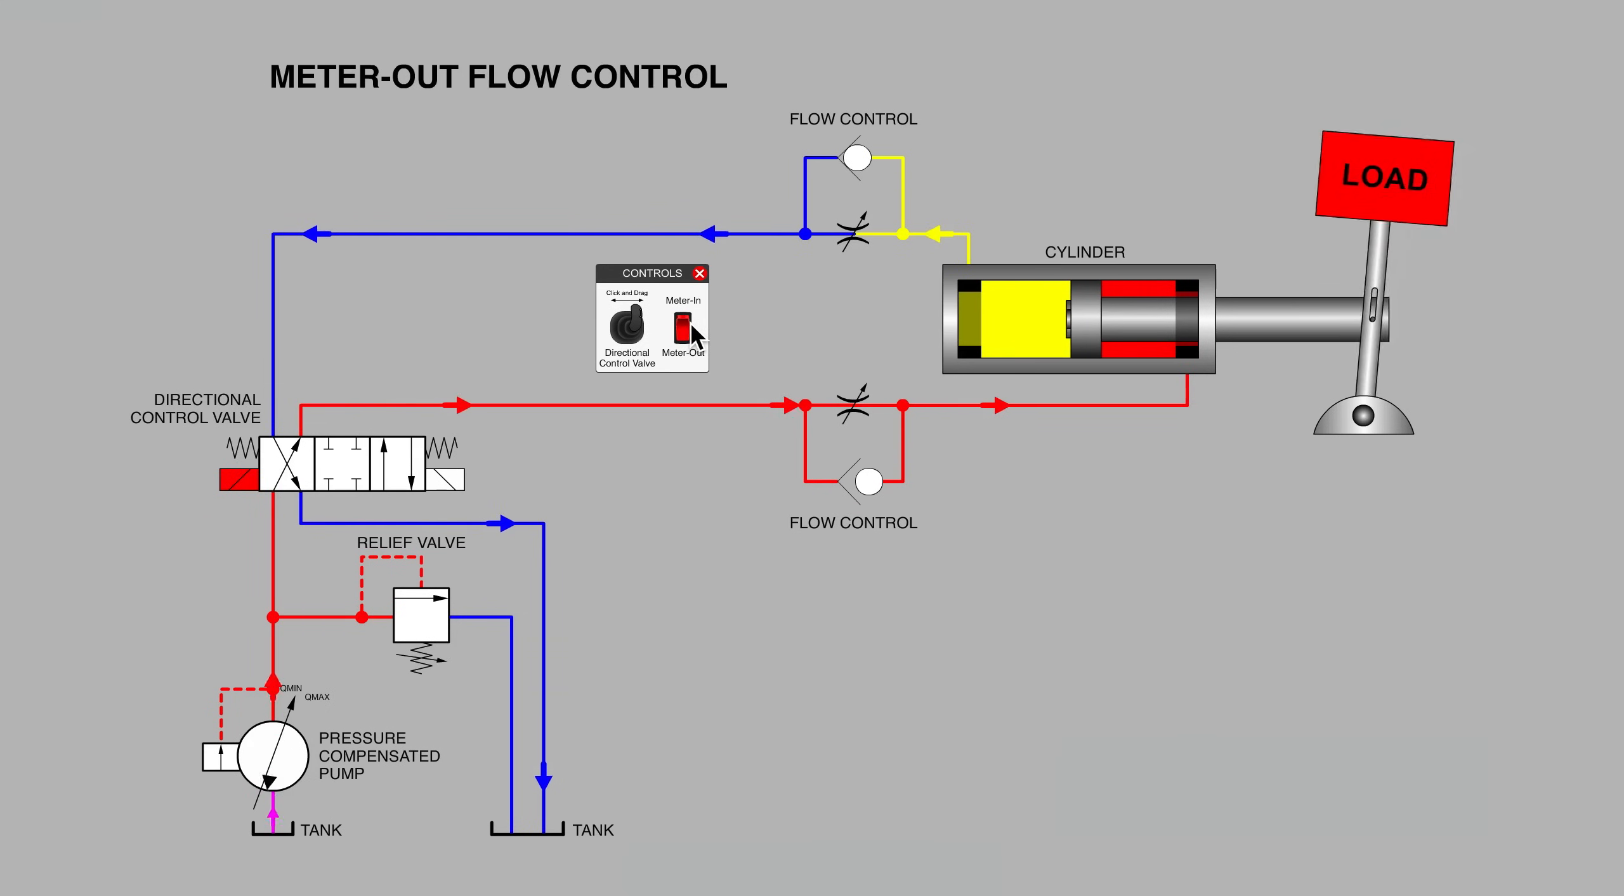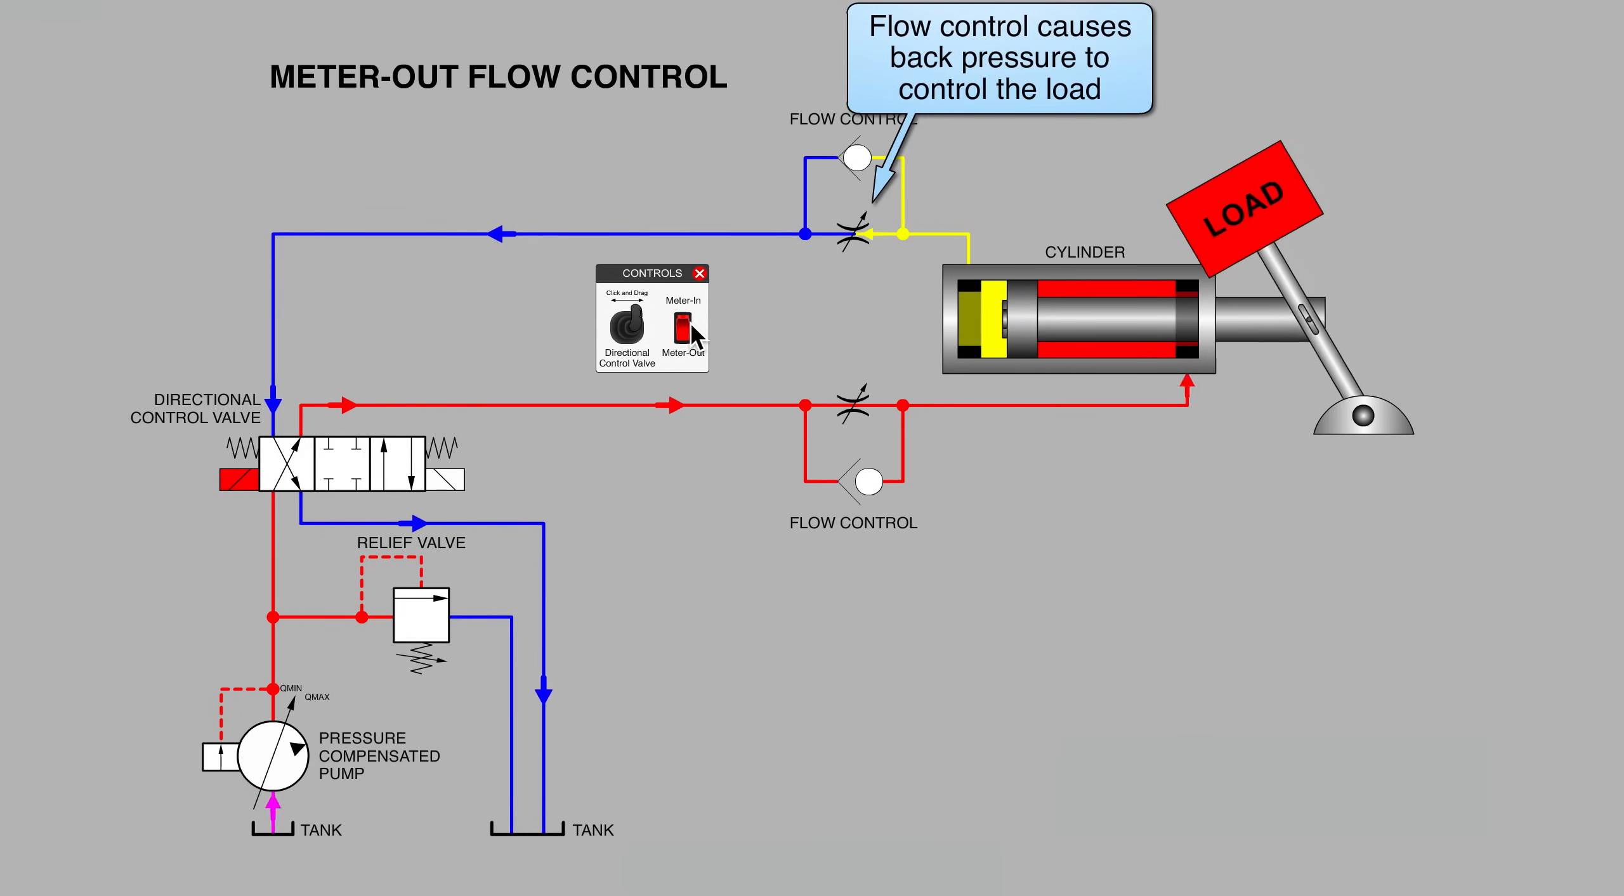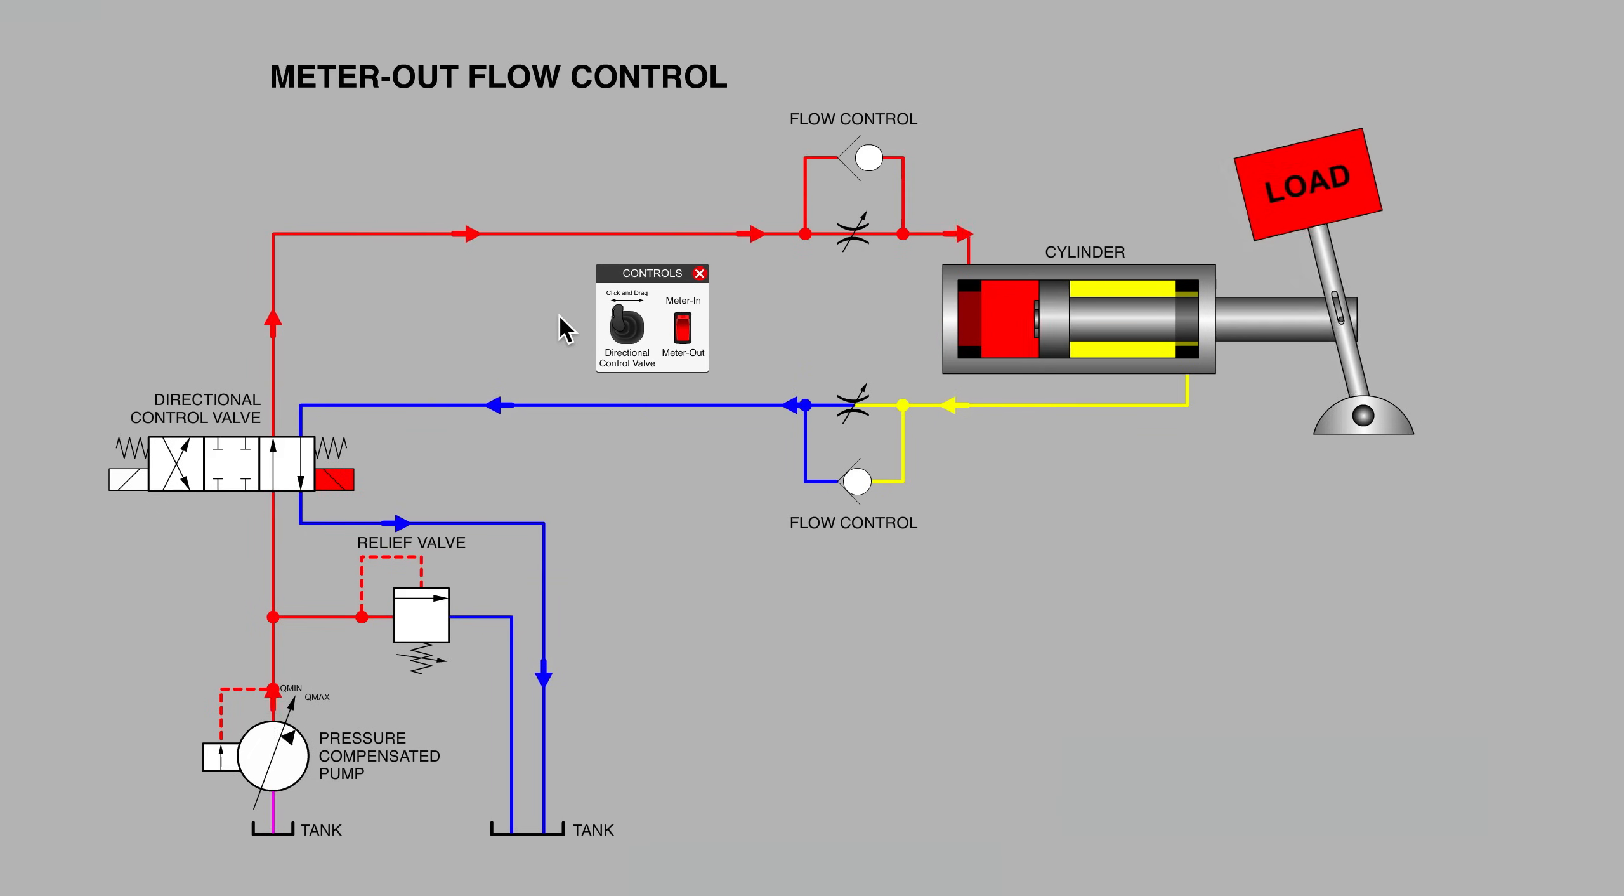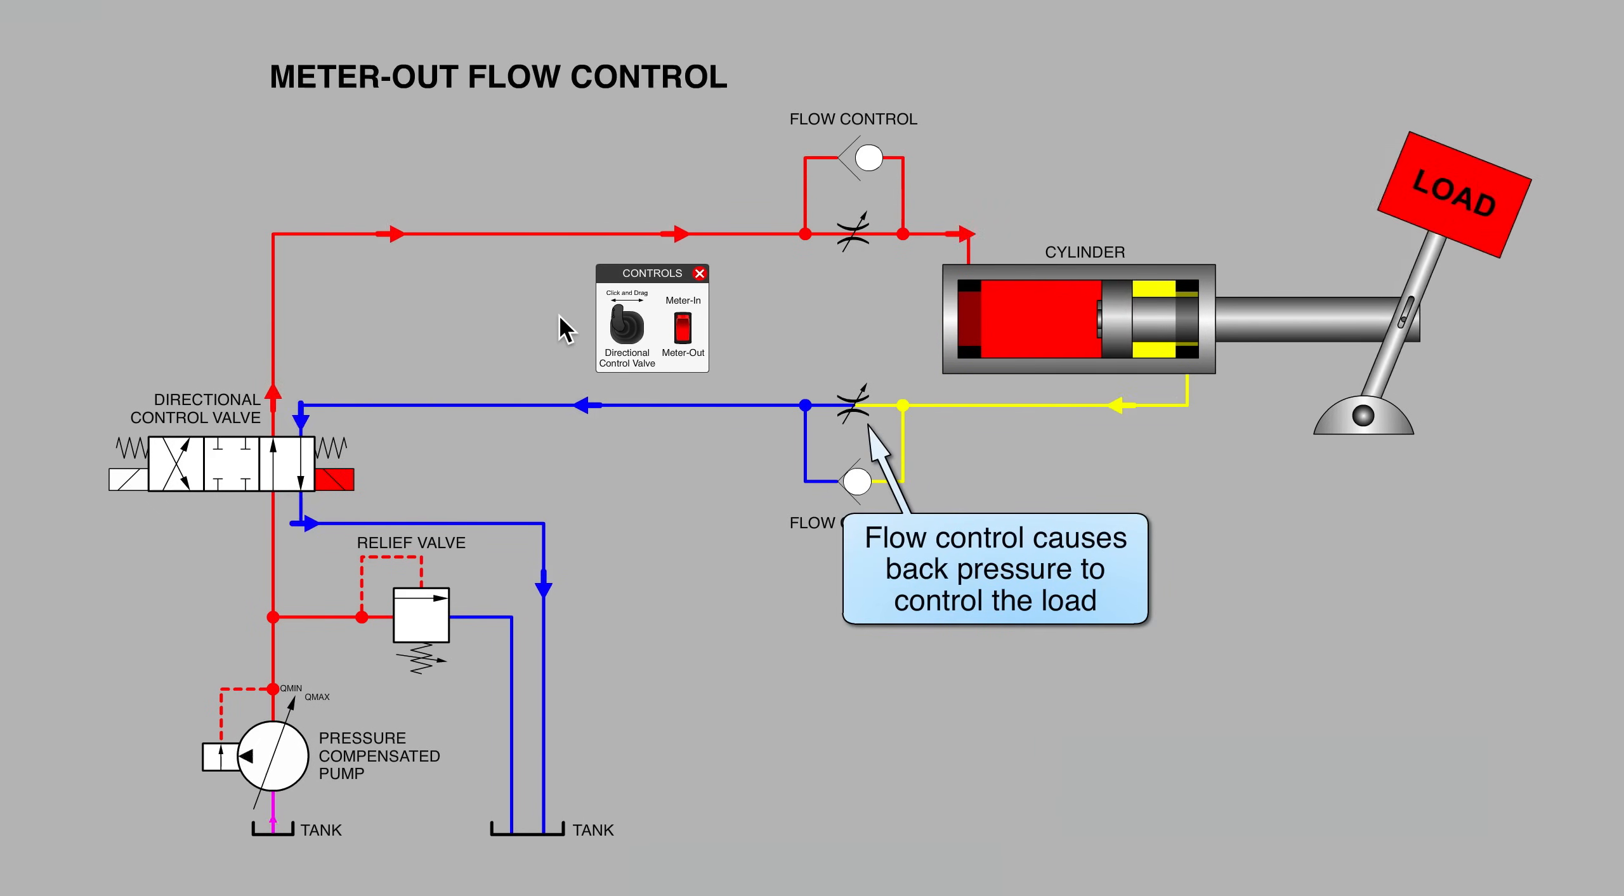But don't be in a rush to apply meter out to the rod end port. This particular meter out arrangement here can come at a pretty high price to the damage that it can cause in your hydraulic system. If this particular variable orifice, if this needle valve is pinched down too far during extension, believe it or not...